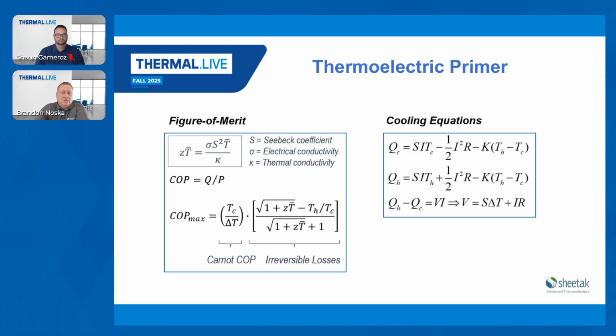Another important equation is the COP, the coefficient of performance, and that is basically how much the device is cooling, so your Q that the cold side is absorbing, over the electrical input that the thermoelectric requires to power to generate that delta T and to actively cool that Q. And in most cases, for low temperature differences, the COP can be high, it can be above 1.